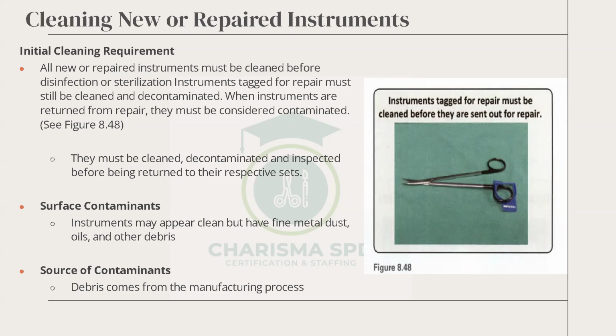Good job. The first step is to clean it. That's our anthem. It has to be cleaned. You don't know what they did to it at the repair shop. You don't know who touched it and where it went. It was exposed to so many things. So as the number one rule, consider it dirty when it comes in. So it goes straight to where? The decon. You register it in the decon, you rinse it off, flush the lumens and all the suctions, and then put it in the washer before it goes back to the clean side. Are we all okay with that?